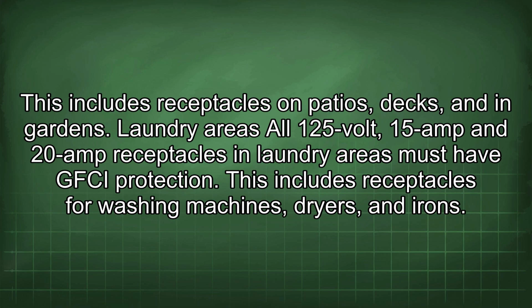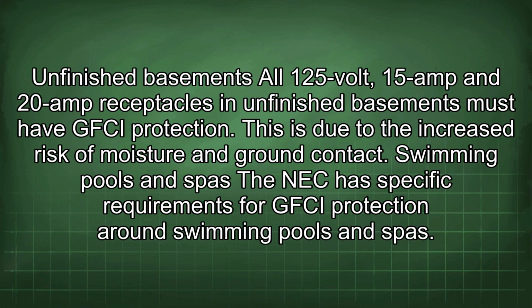Laundry areas. All 125 volt, 15 amp and 20 amp receptacles in laundry areas must have GFCI protection. This includes receptacles for washing machines, dryers, and irons. Unfinished basements. All 125 volt, 15 amp and 20 amp receptacles in unfinished basements must have GFCI protection. This is due to the increased risk of moisture and ground contact.